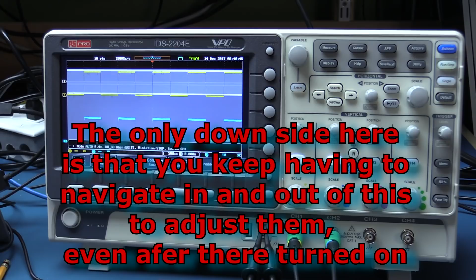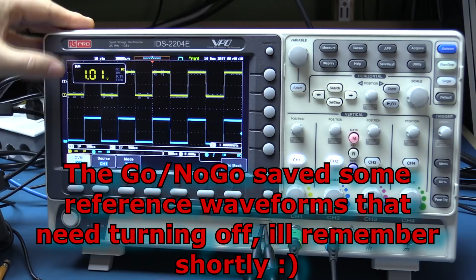So now we have the DVM down here. Some of the go-no-go displays look like they're still just showing. So we turn the DVM on, we're measuring channel 1. This is measuring the DC, so this is 2 volts peak to peak, but it's centered around 0. So it's telling us it's 1 volt. Mode, we can change that to be AC RMS, which is still going to be around about 1 volt, not quite. DC, duty cycle, that's 50%, which is correct. The frequency, which is exactly 1.0000 kilohertz.